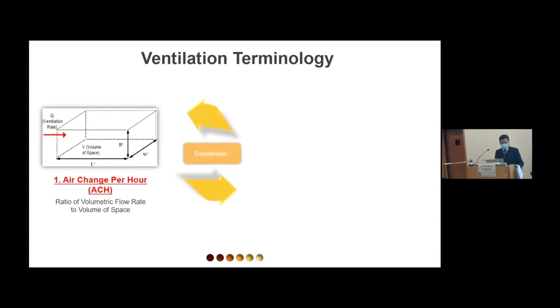The second term is ventilation flow rate, or in short, ventilation rate. It is generally expressed in liters per second. You will see this term commonly used in statutory regulations, codes, and engineering standards. Usually, the requirements state the minimum ventilation rate per person. So for places where the number of persons may vary from time to time, the air change per hour would change due to its occupancy status. The formula shown on the slide simply defines the relationship between the air change per hour and the ventilation rate. It is simply the ventilation rate multiplied by the time and divided by the room volume.